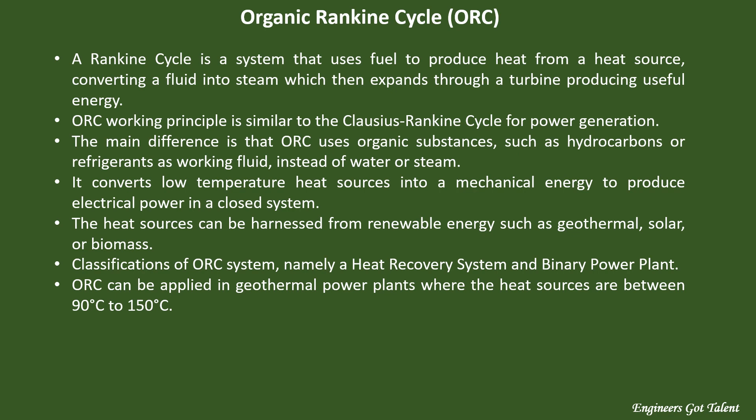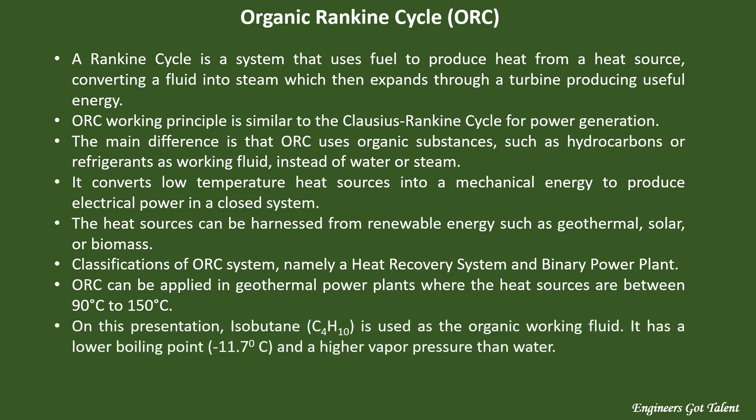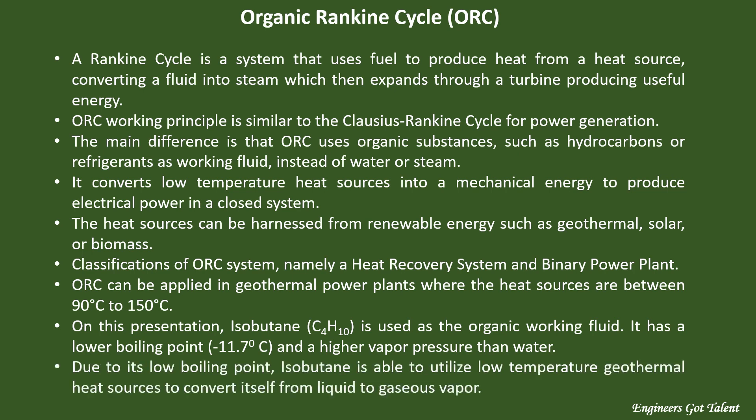ORC can be applied in geothermal power plants when the heat sources are between 90 degrees Celsius to 150 degrees Celsius. In this presentation, isobutane with a chemical formula of C4H10 is used as the organic working fluid. It has a lower boiling point of only minus 11.7 degrees Celsius and a higher vapor pressure than water. Due to its low boiling point, isobutane is able to utilize low-temperature geothermal heat sources to convert itself from liquid to gaseous vapor.